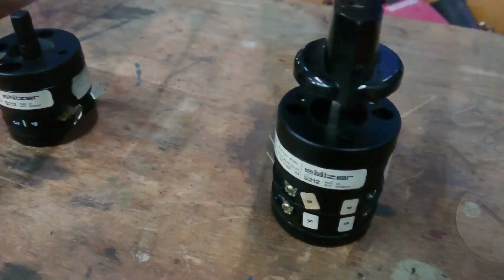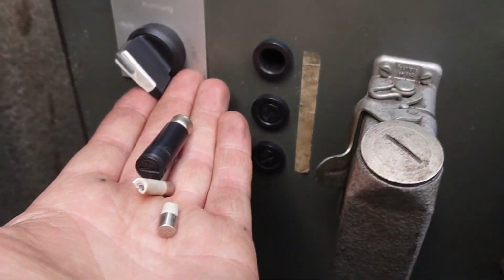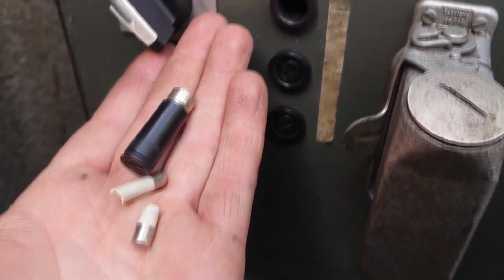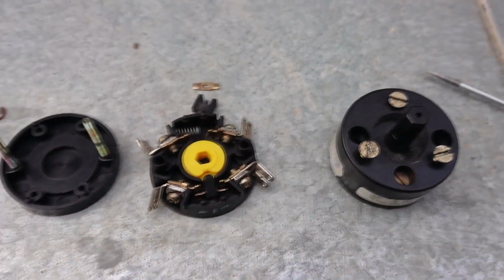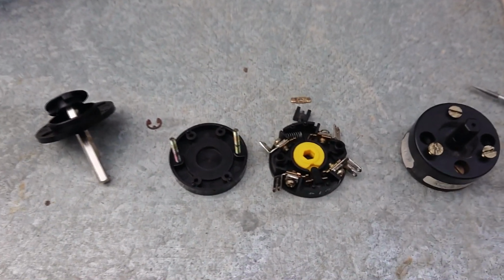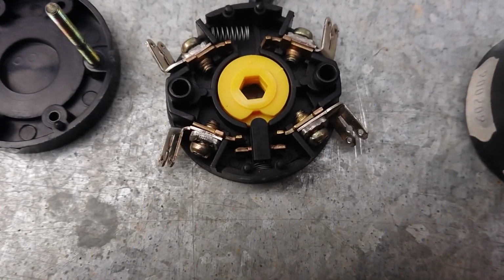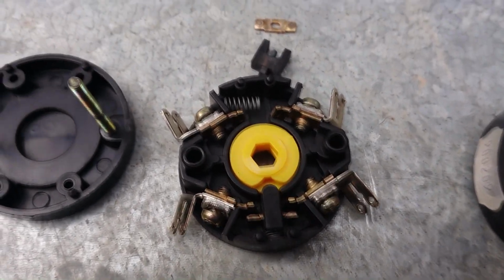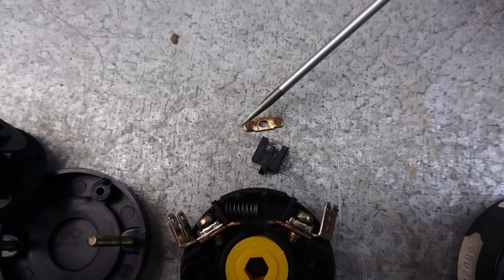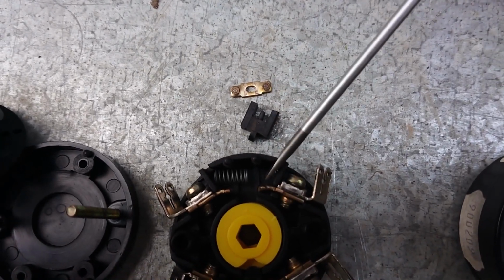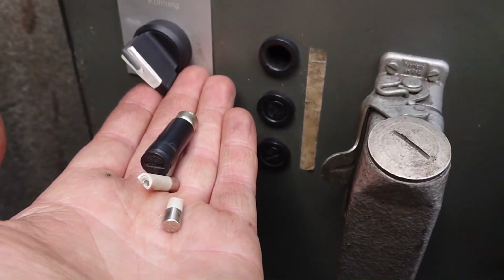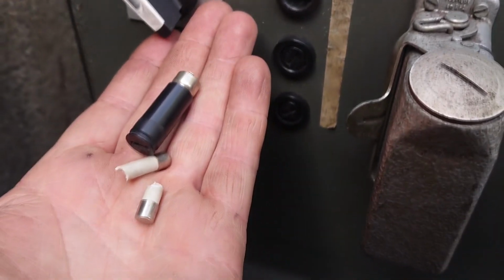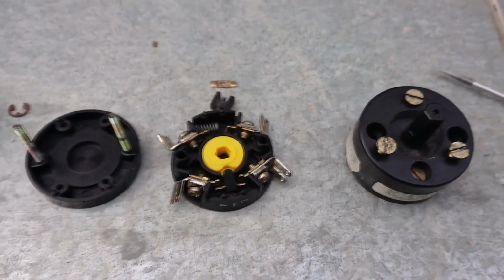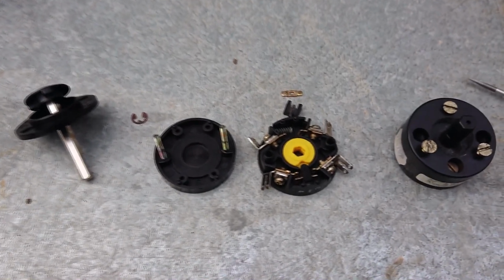But let's take a step back here. The fuse is blown and the switch is also broken. Some people would now assume the broken switch must be causing the blown fuse. I'm afraid that is not the case. A fuse blows when there is an overcurrent or, in extreme cases, a short circuit. The switch, however, cannot really create these conditions, at least when it's not just a molten lump of plastic. Quite the opposite - the switch doesn't cause a short, instead it doesn't even close. So here's my explanation: something else caused an overcurrent and the fuse kept blowing, and whoever worked on the machine then bypassed the fuse with a piece of wire, for example, so that the switch was overburdened and its contacts were damaged.